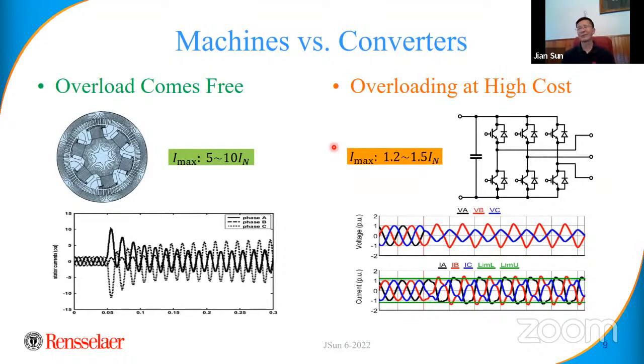For converters, well, you can do that. If you want to take 10 times more current, you can do it, but you have to put 10 times more semiconductor devices in parallel, right? Because every device is rated for a certain current. And the time constant for the device to fail on overcurrent is milliseconds, so you cannot put that much current through a semiconductor device for more than just a few microseconds. To handle these large short circuit currents, you have to put a lot of semiconductors there. That's going to be really expensive, and not many people are willing to pay for that. In typical converter design, we rate the semiconductor devices for 20, maybe up to 50% overcurrent. Not 5 times, because that's not economical, right?